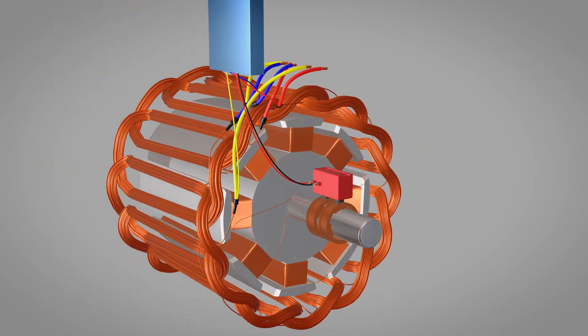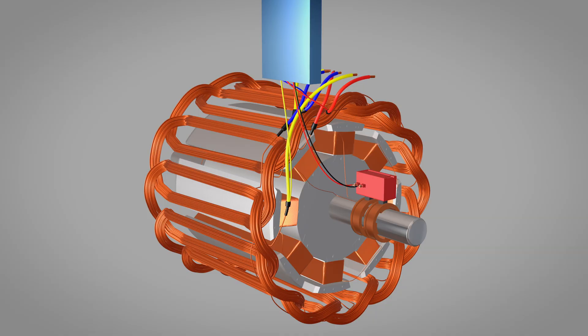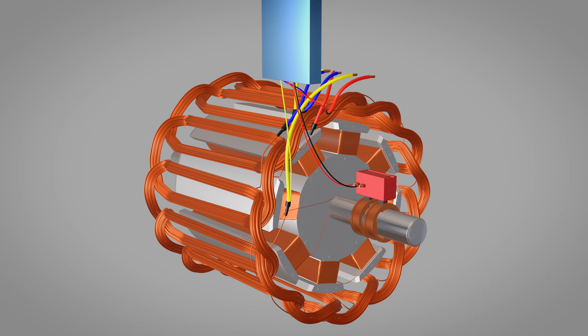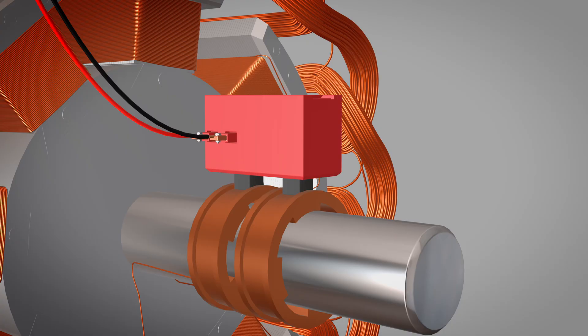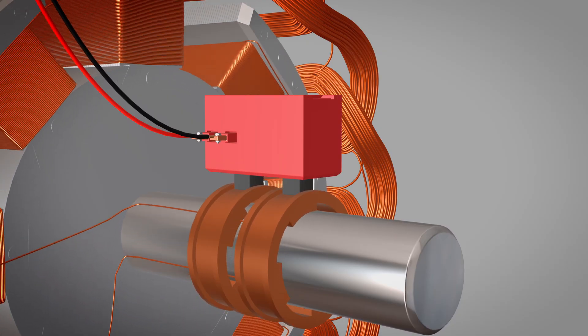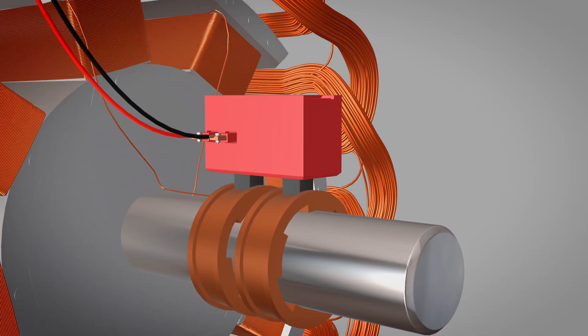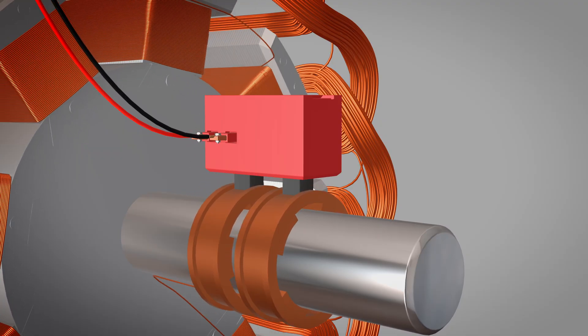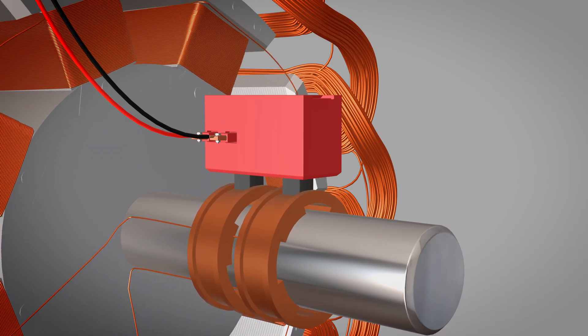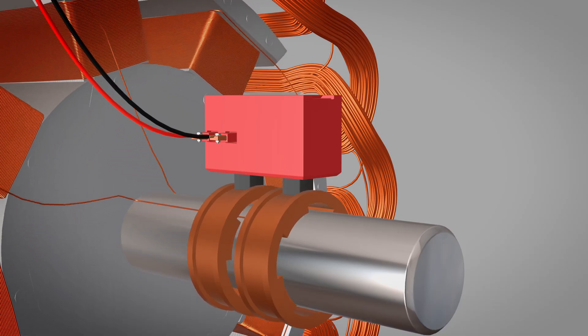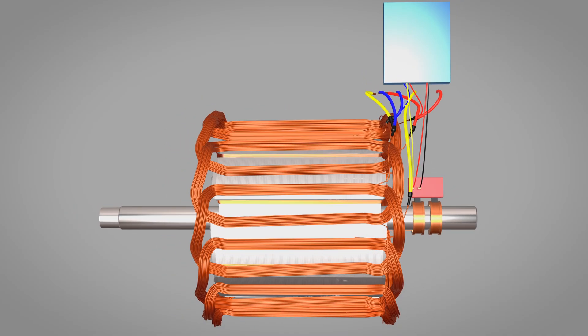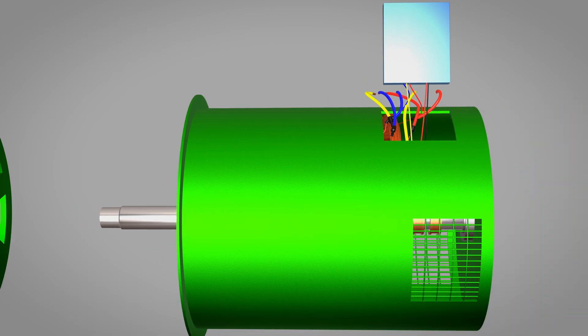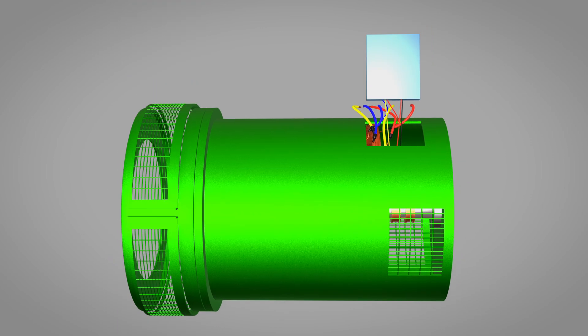While brushed DC excitation systems have served us for decades, they come with significant drawbacks that impact both reliability and operational costs. The fundamental issue lies in the mechanical contact between carbon brushes and slip rings. As these components slide against each other during operation, they create inevitable wear that demands constant attention. This wear process generates carbon dust that contaminates the electrical environment, degrading insulation and requiring frequent cleaning to maintain safe operation. This is precisely why modern alternators have overwhelmingly adopted brushless shunt excitation systems, by eliminating brushes and slip rings entirely.